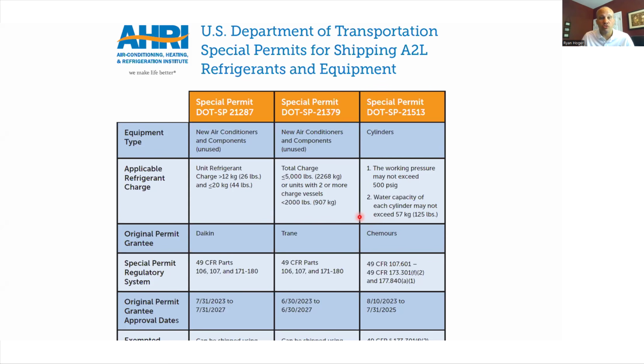If, however, you do need to have any kind of vehicle that is going to be having a piece of equipment with more than 26 pounds of refrigerant in it, you don't have to write your own permit request. You can instead become a party to the Daikin permit. They already have a permit for 26 to 44 pounds of refrigerant. And you could apply for a permit. Instead of typing up all the details, you can just cite their permit number and say, I'd like to use that permit. You still got to do the placarding, right? But you can use that permit.